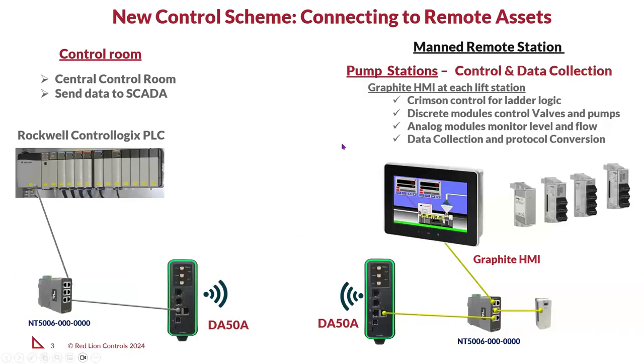Our Red Lion solution: we replaced the PLC and the I/O with a Graphite HMI and our ladder logic Crimson control module, which provides IEC 61131 ladder logic, function block, and statement list capabilities, and gave them control and data collection as well as protocol conversion.